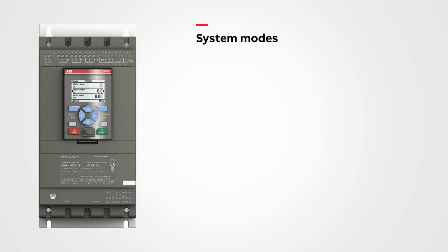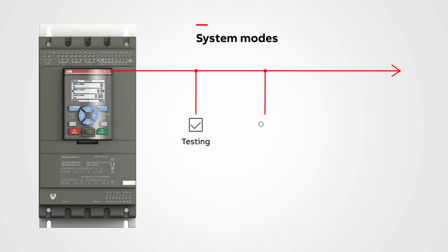System modes are special features built into the PSTX Softstarters that extend its functionality beyond everyday applications and standard usage. These different modes allow you to test, demonstrate, or troubleshoot the Softstarters. It is possible to run the PSTX Softstarter without connecting a motor, test behavior safely during demos, and work with motors smaller than the Softstarter rating. You can check wiring, verify control signals, and explore functions freely.